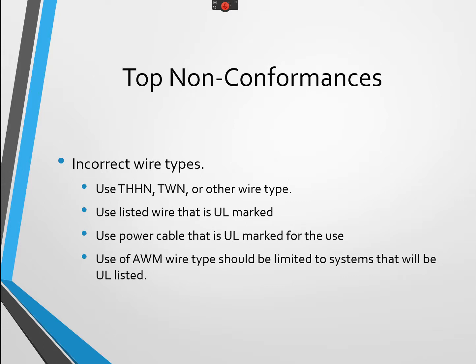Talked about incorrect wire types. We'll have to get in depth with this with yours, but know that particular wire types have to be used with your equipment. Also, the power cable that you plug into the wall to operate your equipment must be UL marked and listed for that use. Buying an unlisted cable, saw this just 2 months ago. The cable was unlisted because it was $1 cheaper per foot, and we weren't able to field label that equipment. We actually had to run down, and this is a different piece of equipment, run down to Home Depot, buy the right cable of the right size with the listing on it, take a picture of the reel with the listing on it, and reinstall it. And this is the appliance and AWM, appliance wiring, machine wiring. That should be limited to systems that are listed.